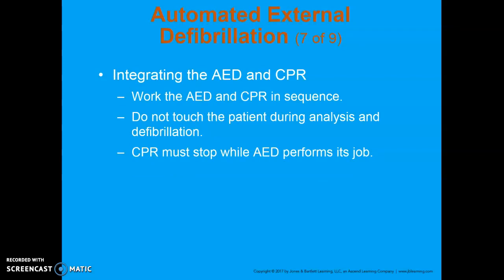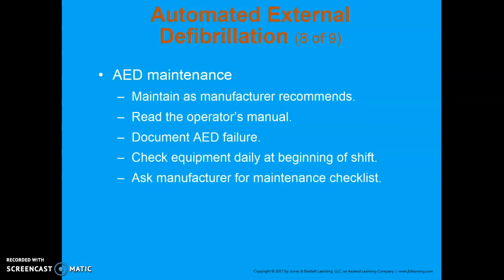We have already talked about some AED CPR stuff, so I'm just going to go ahead and go on to the next one. Maintaining your AED. You need to make sure that you follow the maintenance guidelines. Every manufacturer does have recommendations for how to fix that. So you should be familiar with how that works. The three most common failures of the AED is failure of the machine to shock fine VFib. Fine VFib can look an awful lot like asystole, and so it may or may not shock it. If you apply the AED to a patient who's moving, squirming, or being transported, typically if they're awake and doing their thing, even if they have chest pain, even if they have a dysrhythmia, we're not going to put the patches on them. Just in case, some places do have that in their protocol, but typically you don't need to do that.